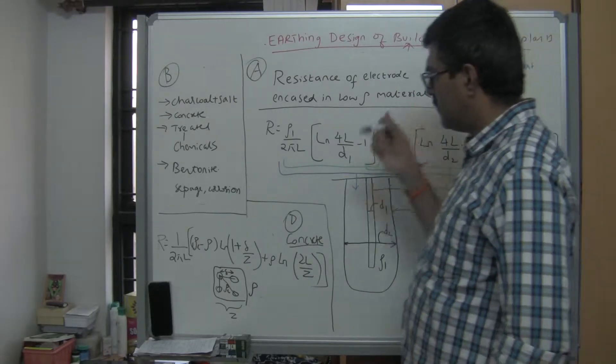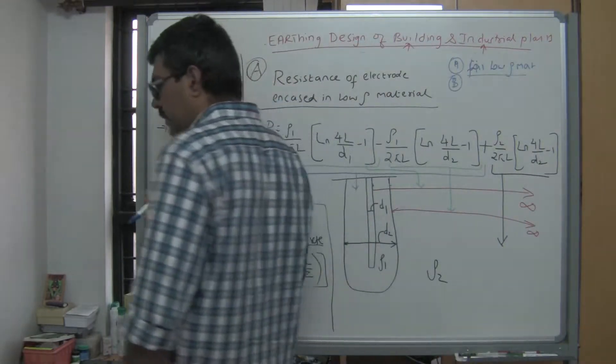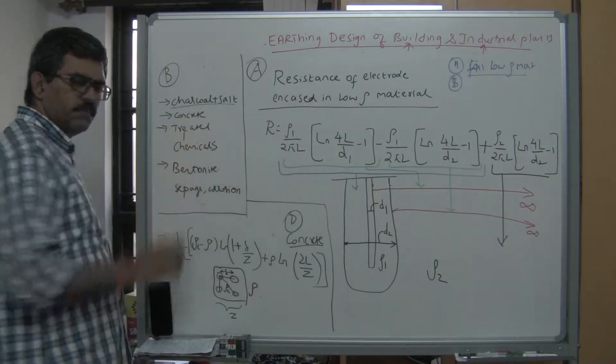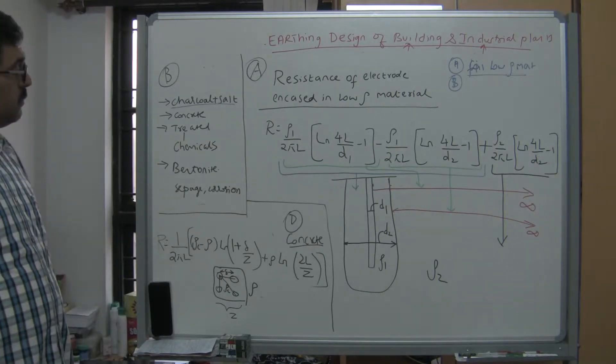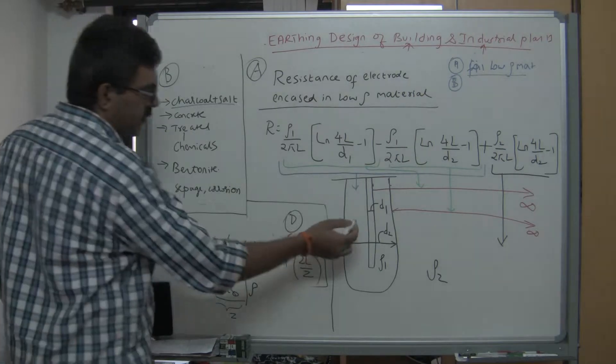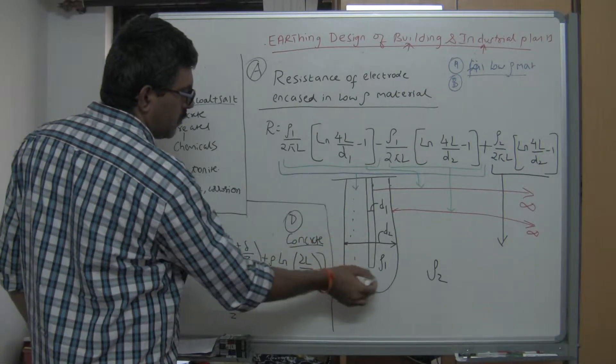You have different types of low resistivity material that you can fill. One is charcoal and salt, but this will lead to a lot of corrosion of the electrode. If you fill charcoal and salt around your electrode, it will undergo significant corrosion.